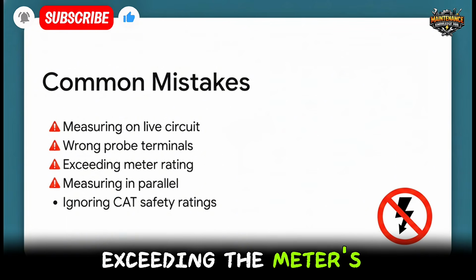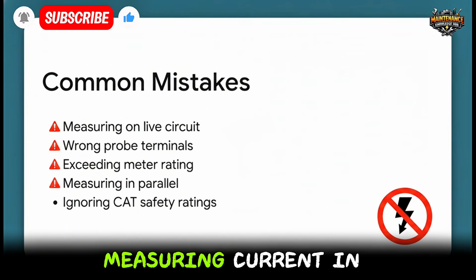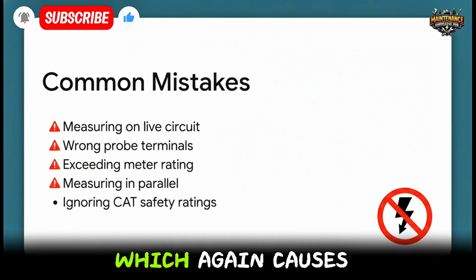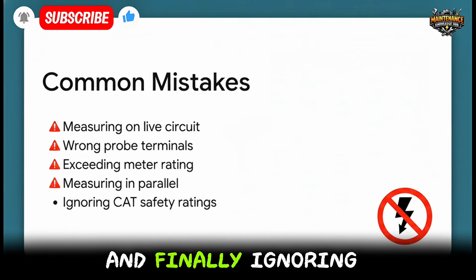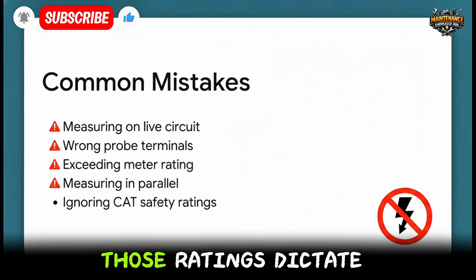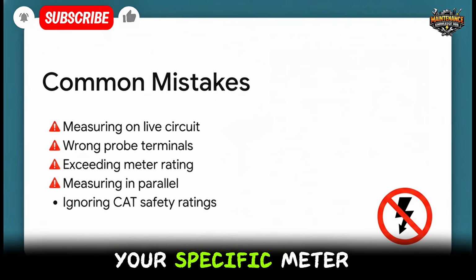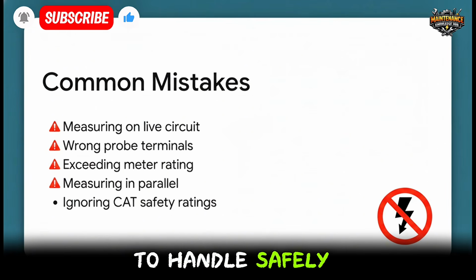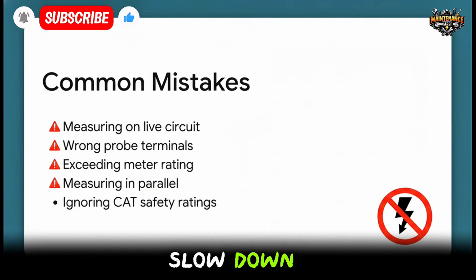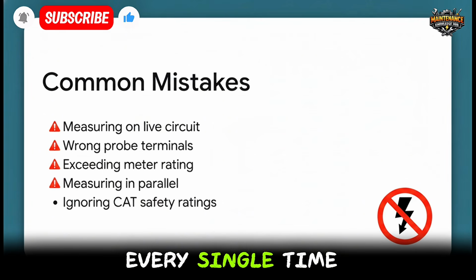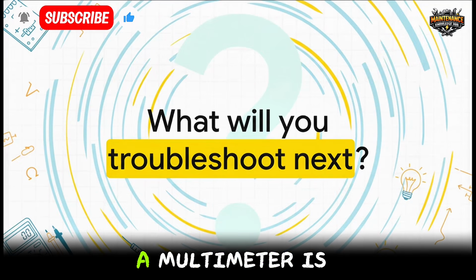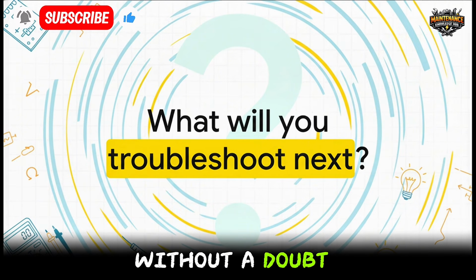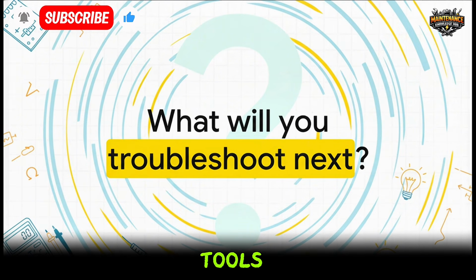Third, exceeding the meter's maximum rating. Fourth, measuring current in parallel instead of in series, which, again, causes a short. And finally, ignoring CAT safety ratings. Those ratings dictate the max electrical environment your specific meter is actually built to handle safely. So stay vigilant, slow down, and just double-check your meter settings every single time. It'll keep you safe.